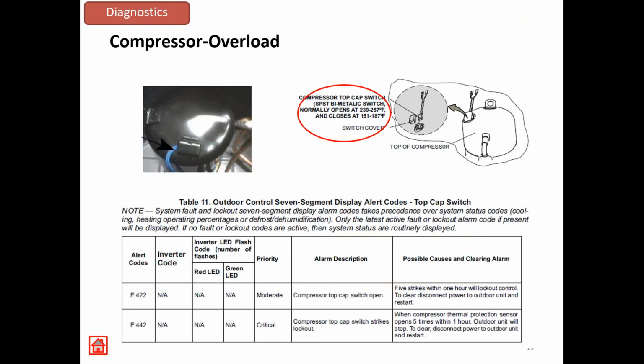But back to this right here, you can actually look at it and say, okay, well, on this date, we had this occurrence. 2 days later, we had the same occurrence, and it eventually got worse. Something's changed. Filter restricted. We're running high compressor demand, something like that. The condenser's clogged up. Mr. Homeowner's been out here and he's got his yard clean and he's blowing stuff up against it. And so that's another thing that comes about as well. So anything that's going to raise the top cap of this compressor to get hot, you're going to start seeing a pattern, and that's really how we're going to help diagnose what's going on.